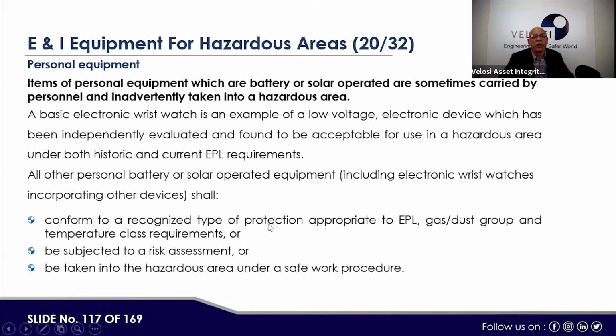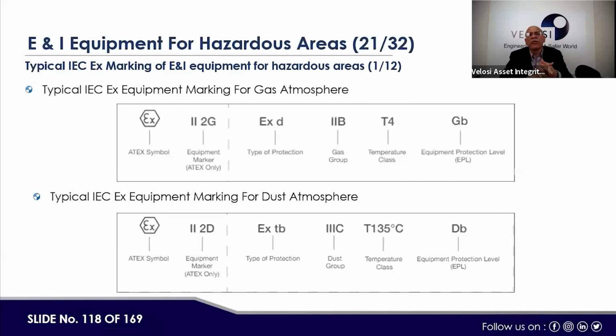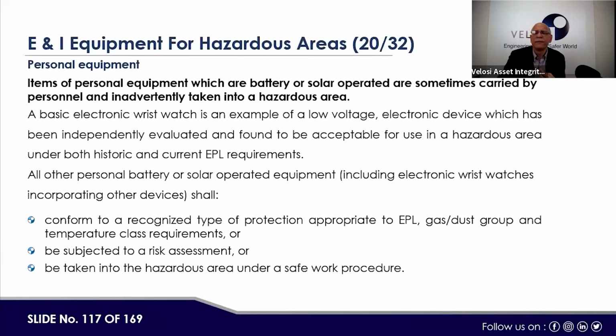It should conform to the recognized type of protection appropriate to EPL, equipment protection level, gas dust group, and temperature class requirement. Three things are there: EPL, gas dust group, and the temperature class requirement, or be subject to risk assessment, or be taken into the hazardous area under the safe work procedure. So three things are important, what we studied up to now: EPL, equipment protection level; up to what gas or dust it can withstand without causing fire or explosion; and temperature class, so that it is not igniting that. Now we have come to a point where any engineer who is not electrical and instrumentation, any layman, needs to remember three things to comply with in a HAC area: EPL, gas or dust protection, and then the temperature.